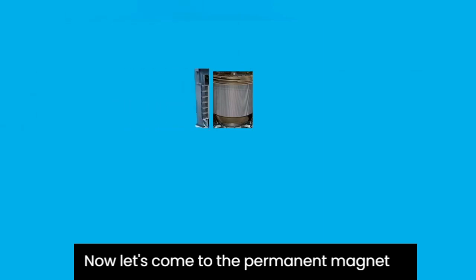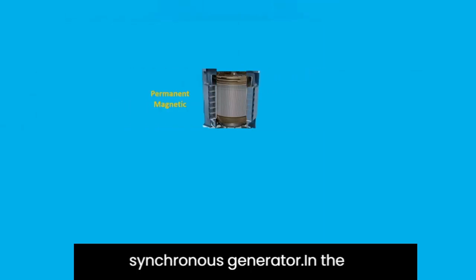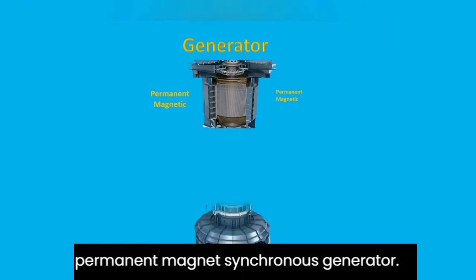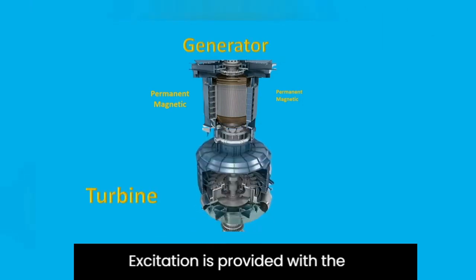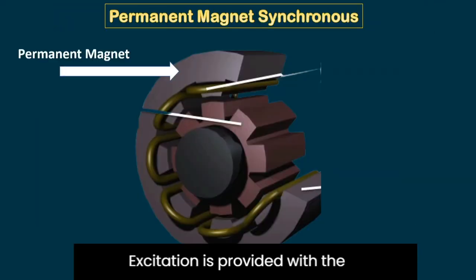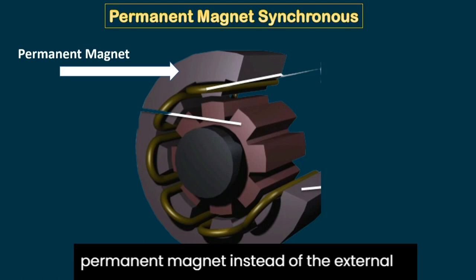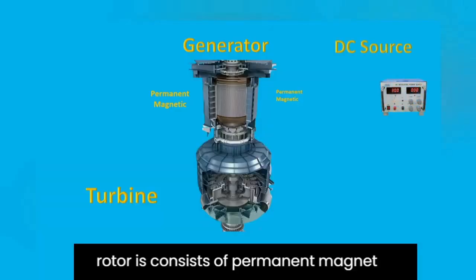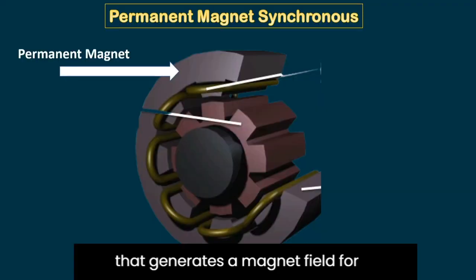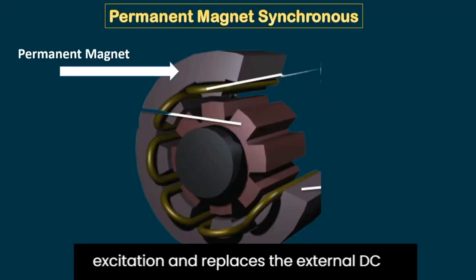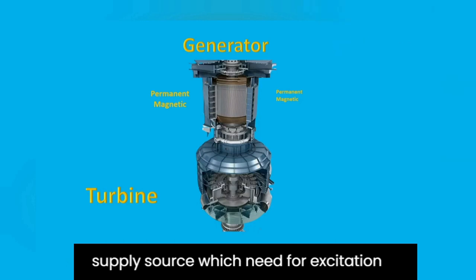Now, in the Permanent Magnet Synchronous Generator, excitation is provided with a permanent magnet instead of an external excitation DC source. Its rotor consists of permanent magnets that generate a magnetic field for excitation, replacing the external DC supply source required in other generators.